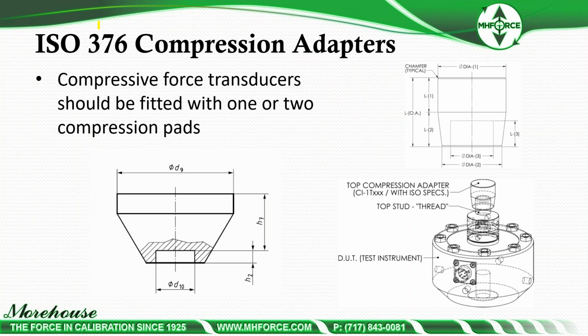So then we talk about compression adapters. Compressive force transducers should be fitted with 1 or 2 compression pads. Here's the drawings for ISO 376. This is a recommendation, and then here's one that we came up with that we've provided. The top stud of the load cell, and then you have a top compression adapter here that's very similar to what's going on here. And then right here we're saying DUT with test instrument, device under test, unit under test, lots of names for it. So yes, we also have compression adapters.